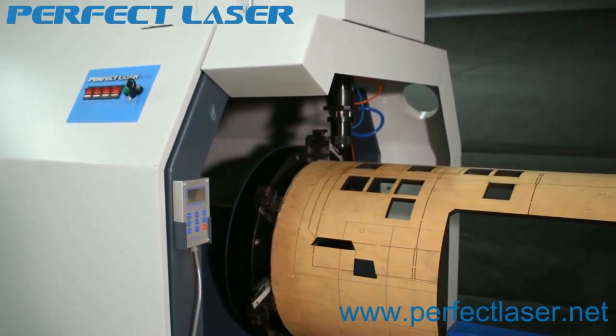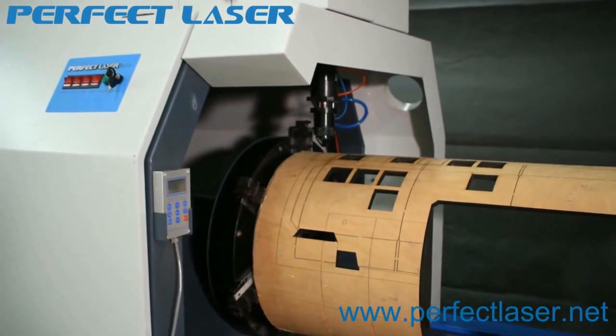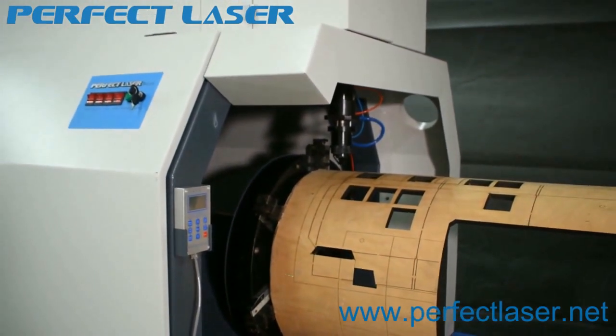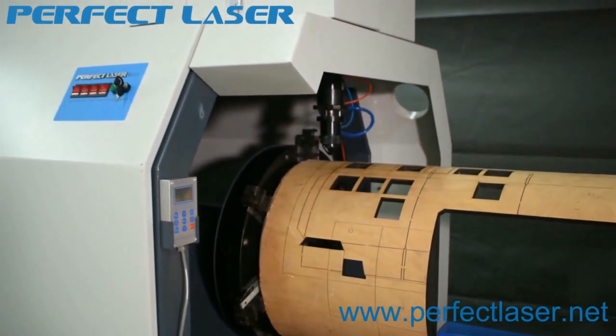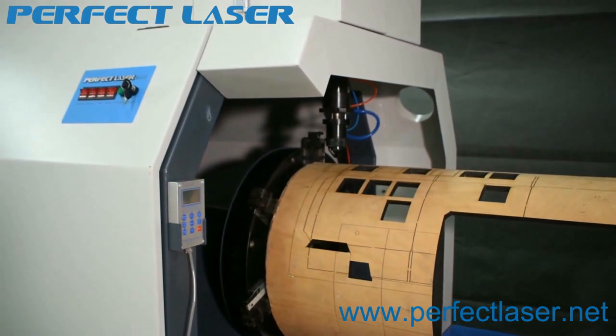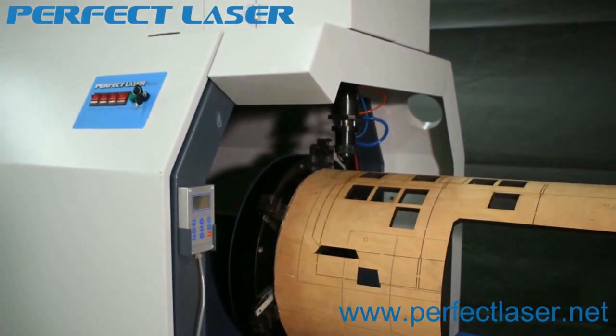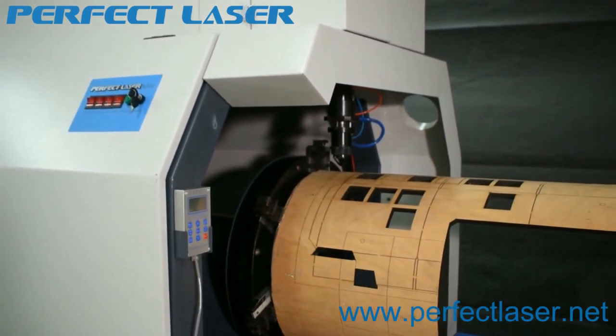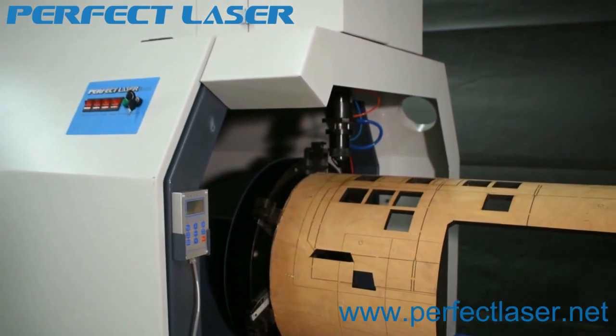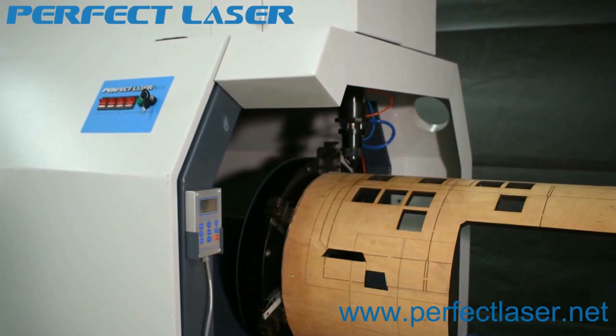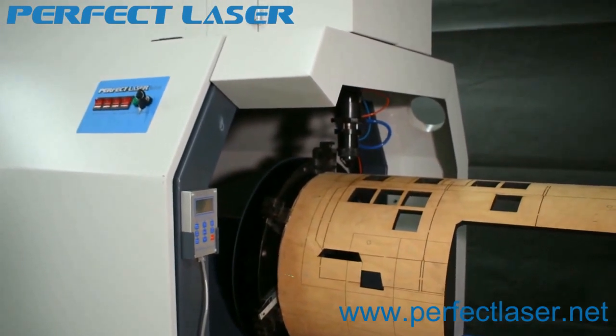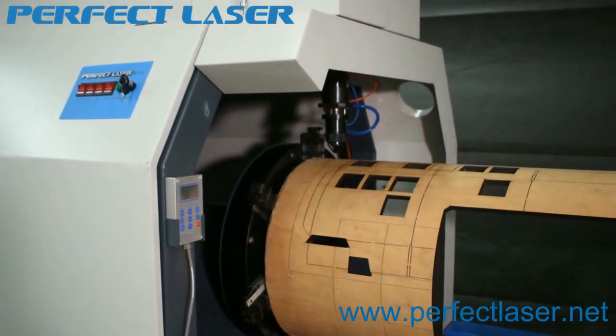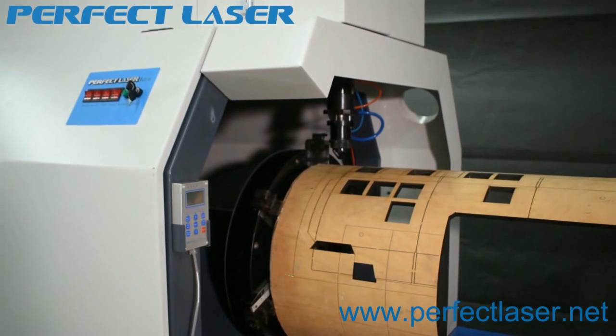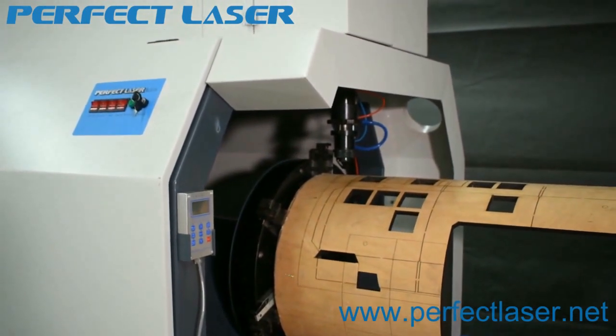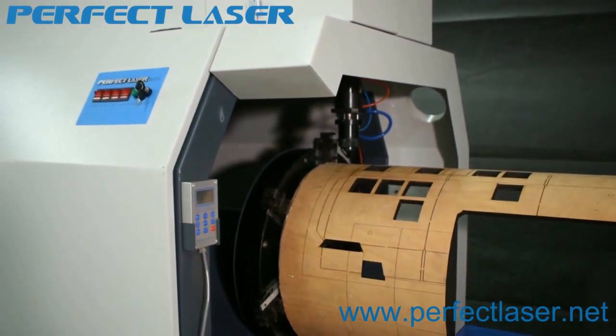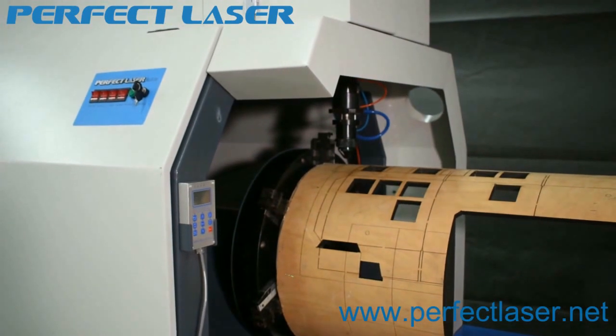For the laser path, we already adjusted the path well before we dispatched the machine. But during the sea shipping of the machine, during the long distance delivery, sometimes the laser path will be a little different. So when you receive the machine, firstly you should check from the center hole to make a laser dot come out and see if the laser comes out in the center of the hole. If it is okay, you do not need to adjust the laser path. But if the laser beam is not in the center of the hole, you need to align and adjust the laser path according to the following method.